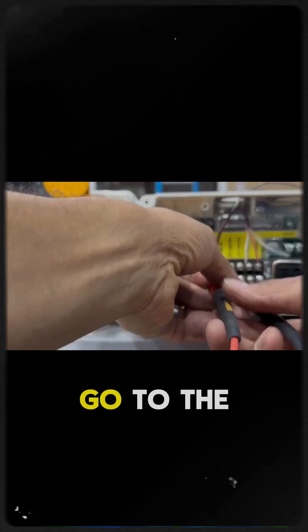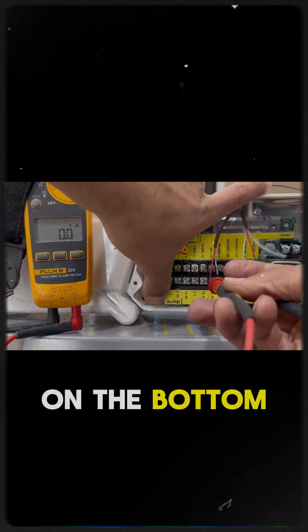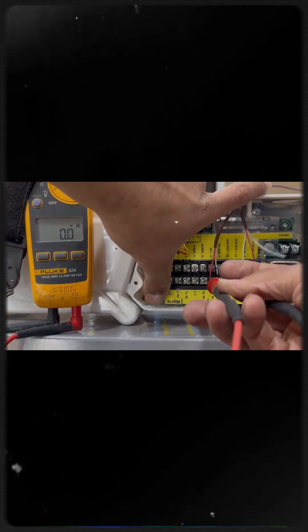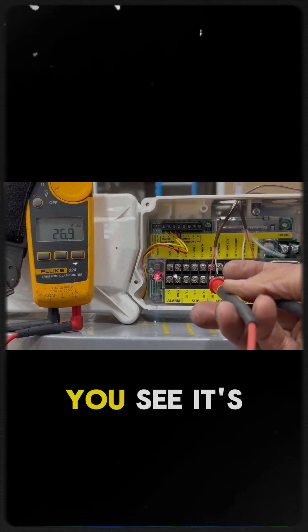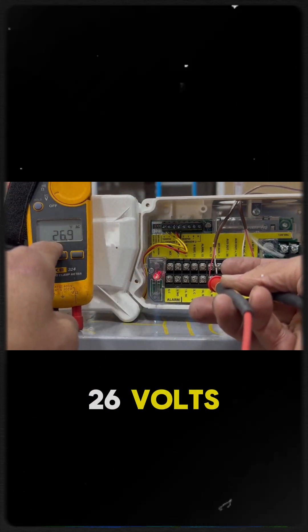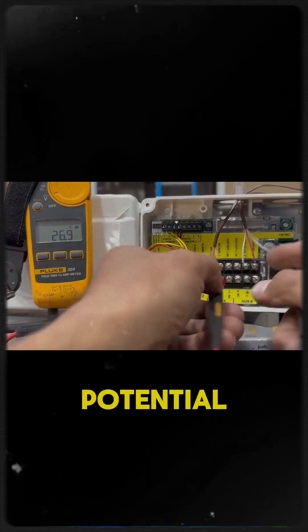Go to the alarm and there's a little button here on the bottom. Press that, hold it, tripped it. You see it's an alarm, I'm just testing it. 26 volts. There is a potential from here to here, so if the sensor there senses smoke, it's going to open.